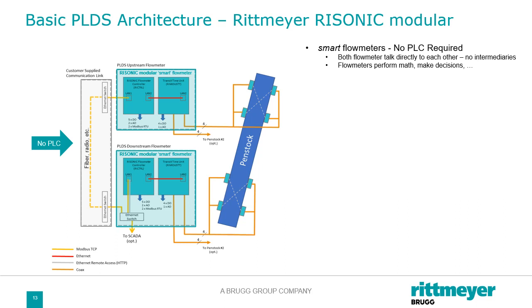These flow meters can monitor more than 1 penstock. A pair of flow meters can monitor up to 4 penstocks. It is a safety system, so we tend to limit that to 2 penstocks as a good trade-off between cost and the ability of a single point failure taking out too much of your protection system.